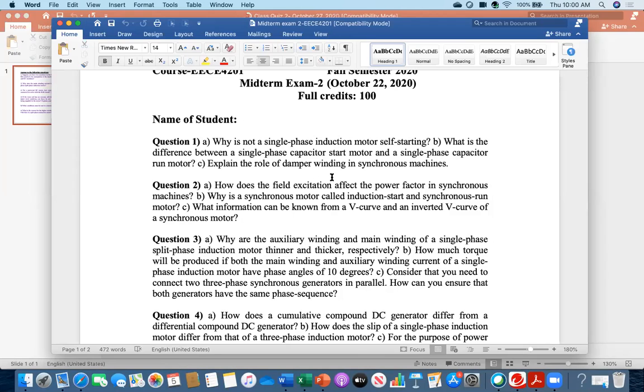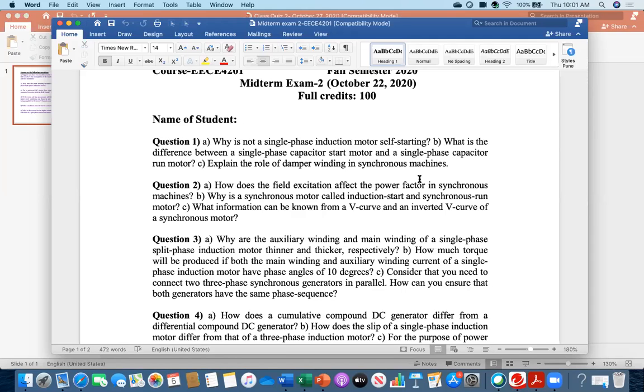Explain the role of damper winding in synchronous machines. When I say synchronous machine, I expect the answer for both synchronous generator and synchronous motor. In case of a synchronous motor, the damper winding is used to initially start the motor, since it is not self-starting. In case of a synchronous generator, the damper winding is used to eliminate the hunting effect.